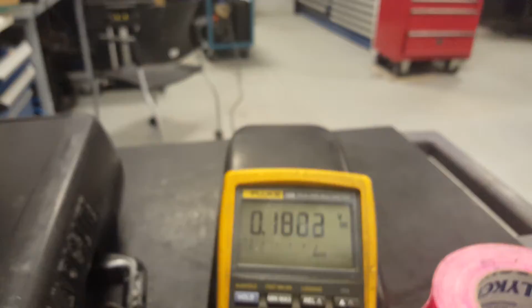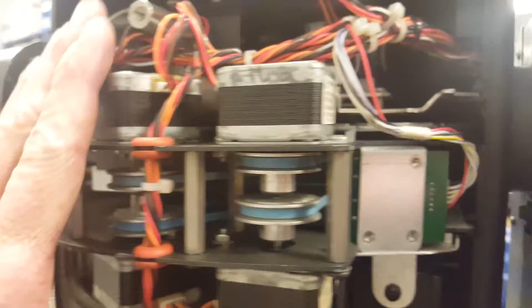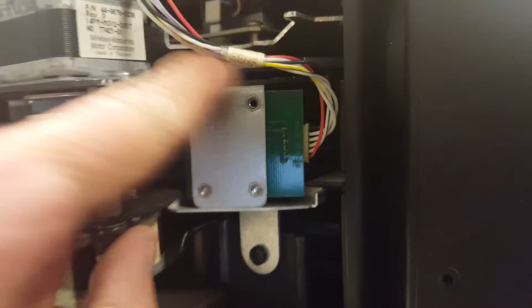So if we remember on the cyan, it stayed at 5 volts, even though the motor is running and the black spot on the wheel is going through the sensor. Since the wheel spins freely, we know that part is okay. So since it's not moving here, it could be the wiring from your sensor board to your MCB - you should check the wiring - but more than likely it's the sensor, since it stayed at 5 volts and didn't go down.